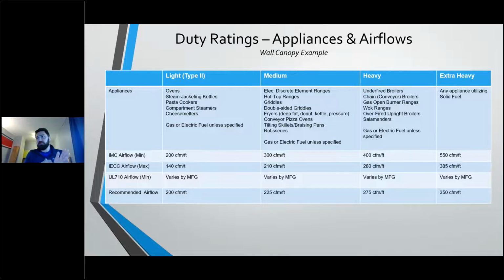So hoods, and again, review for a lot of folks, but got to cover it, hoods are going to be designed based on linear feet of hood. So we're going to come down here, and we're going to see that the IMC airflow minimum rate for a heavy duty hood is 400 CFM per foot. Now, IMC section 507 states that if the hood manufacturer is UL 710 listed, then that manufacturer's UL listing supersedes IMC minimum. So you're going to have a UL 710 airflow minimum.